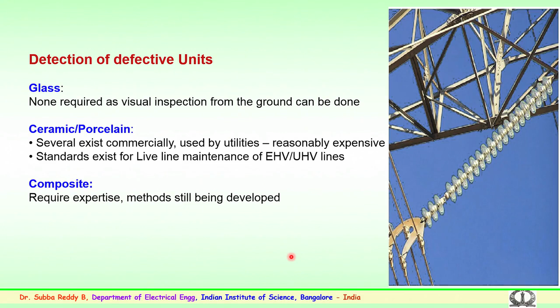These are reasonably expensive, and standards also exist for live line maintenance and for measurement of field to find out whether the insulators are faulty or good. For composite insulators, it requires a lot of expertise. As mentioned, these are of recent origin. There are methods still yet to be developed for the maintenance, live line washing and cleaning of composite insulators, and also methods for detecting faulty insulator strings. Presently these are some of the methods.